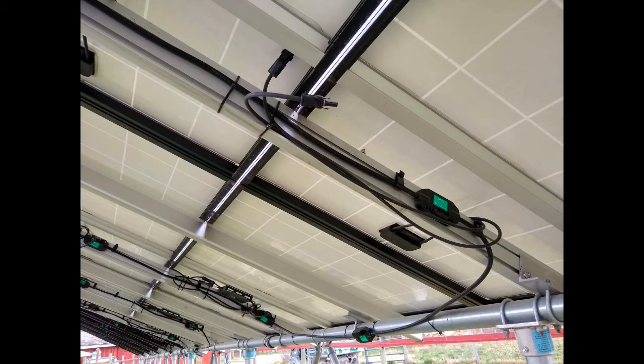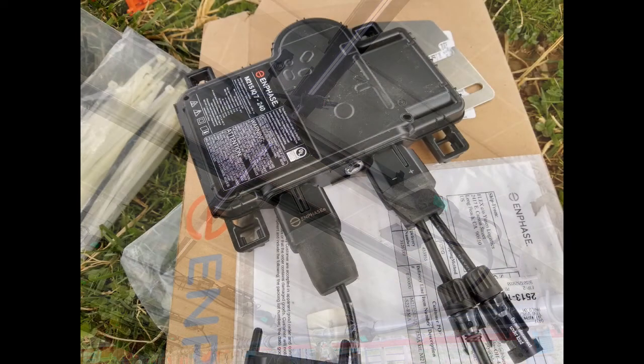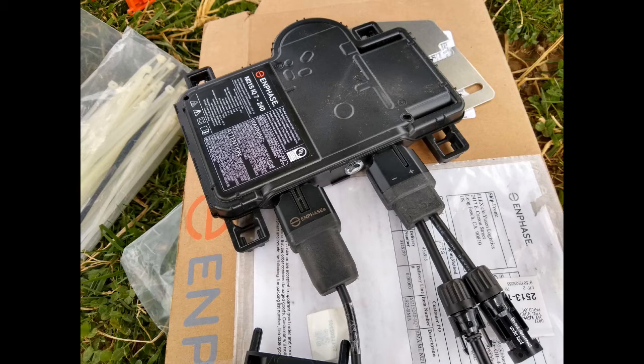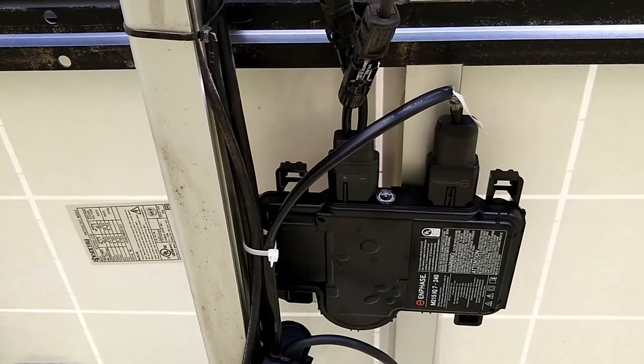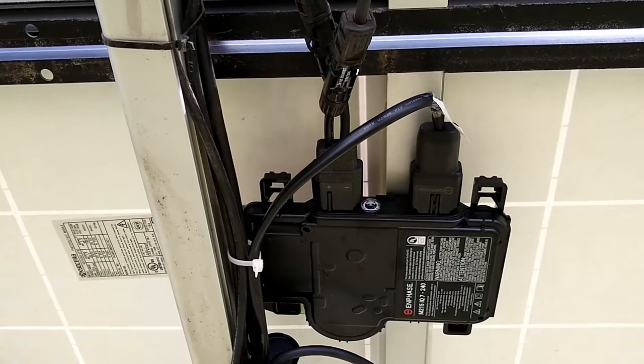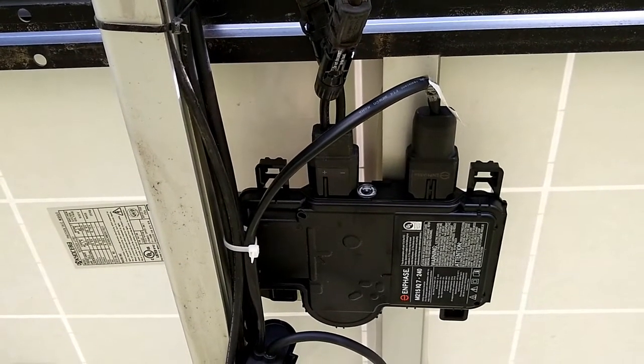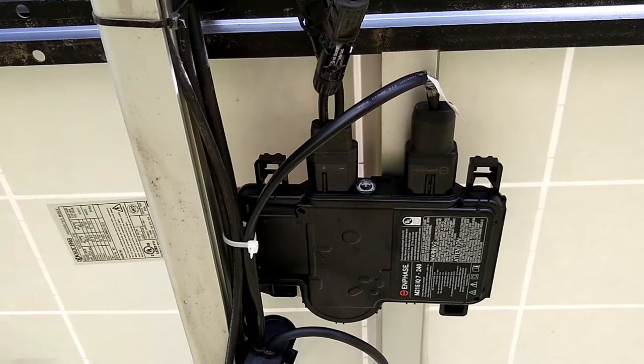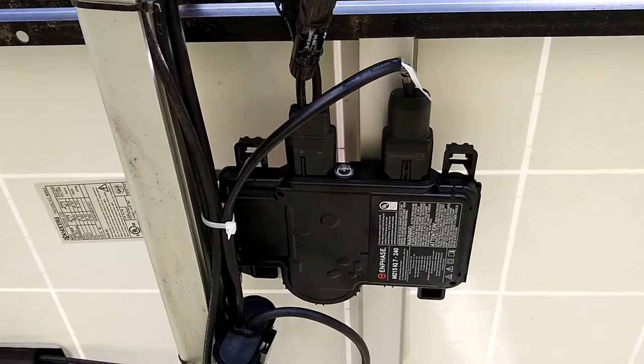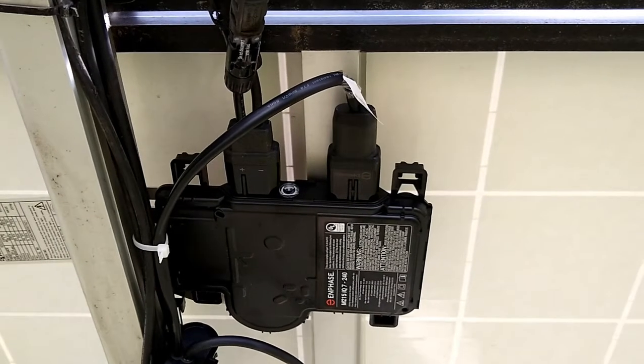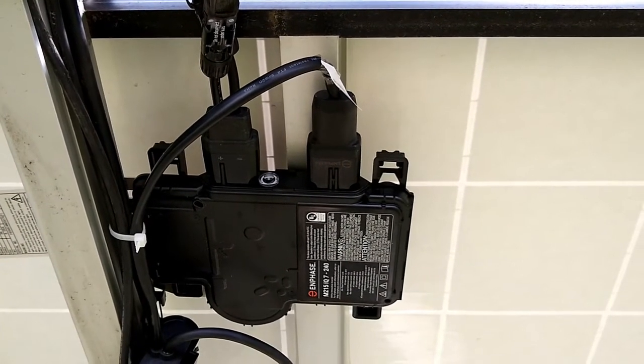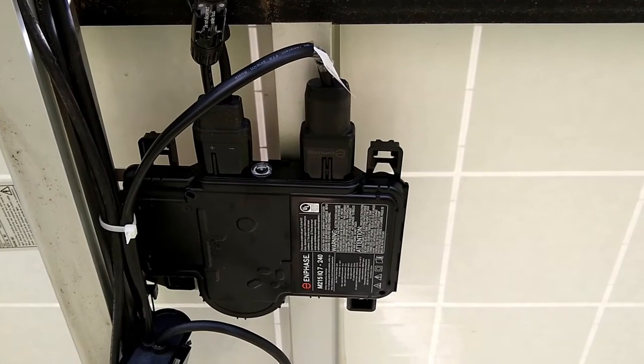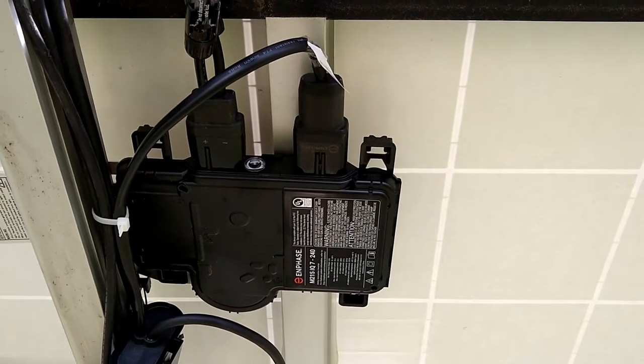Then I removed that microinverter - this is a ground mounted system so it's pretty easy to get in there and remove it without removing the panels. Then attach the cables to the new microinverter - there's only one way they can go so it's not a big problem there. Then I hooked that unit back up and mounted it back on. Then you can see the red light starts flashing - that's an indication that the grid is not being sensed. I turned the system back on, and about five minutes later sure enough the green light came on. It recognized the inverter and it is at this point beginning to generate some power.